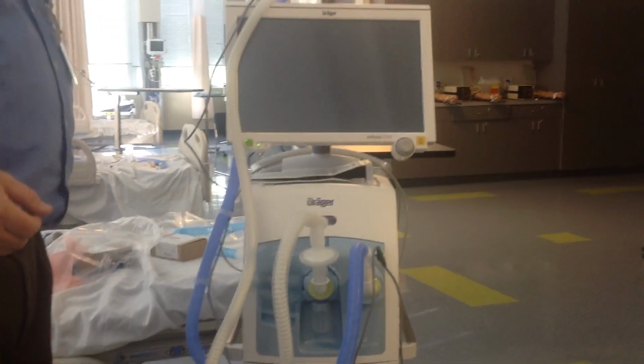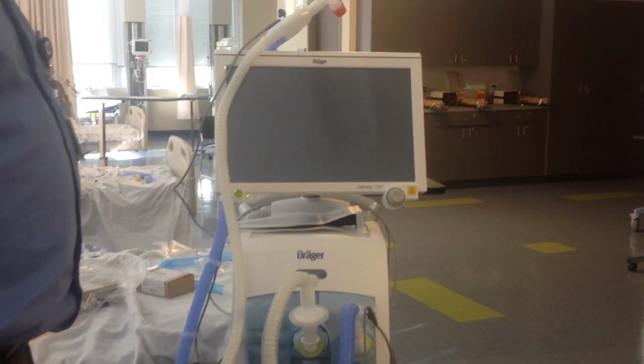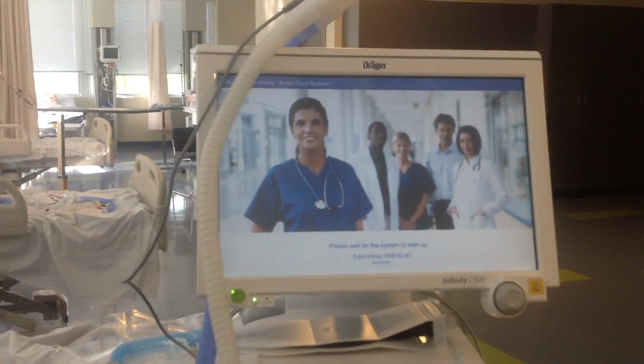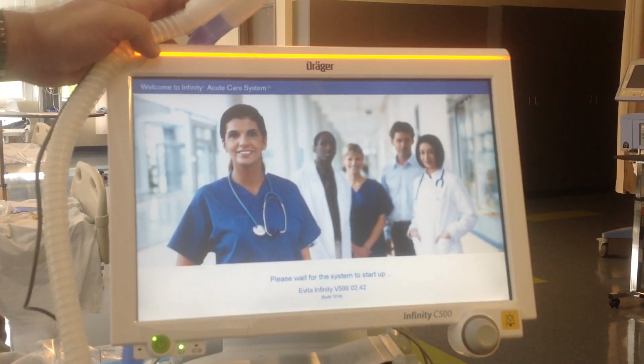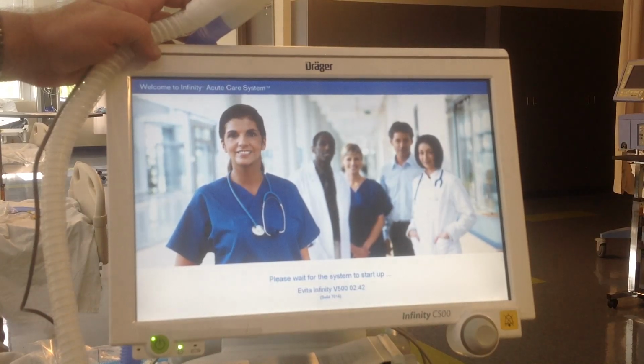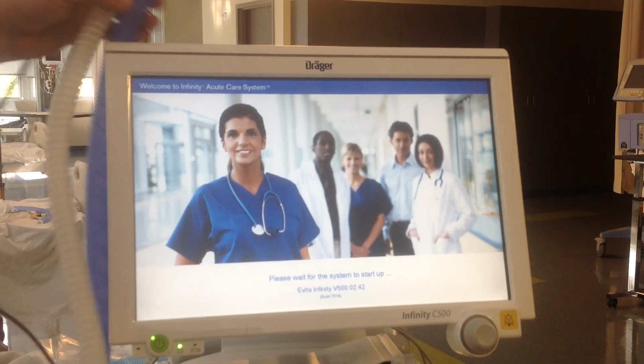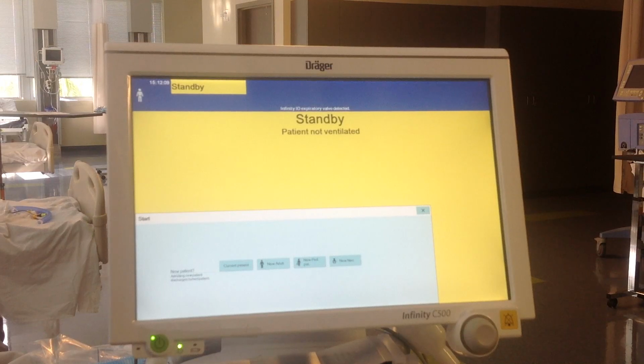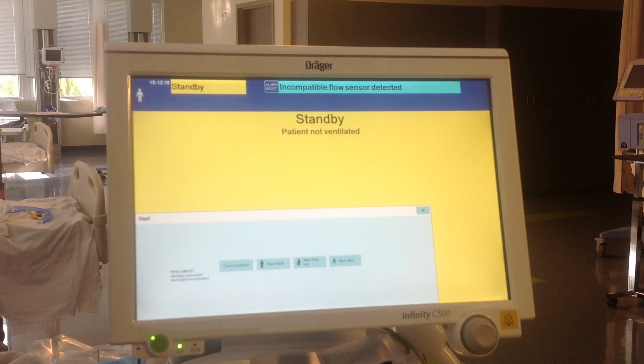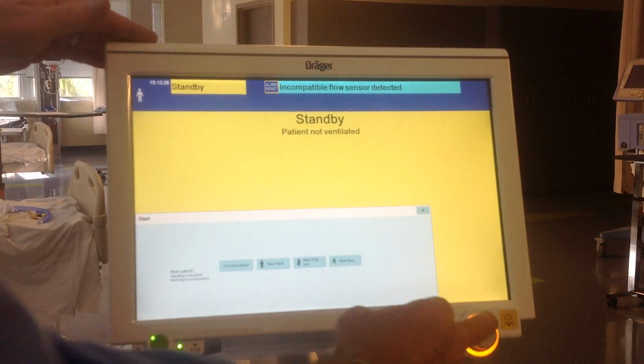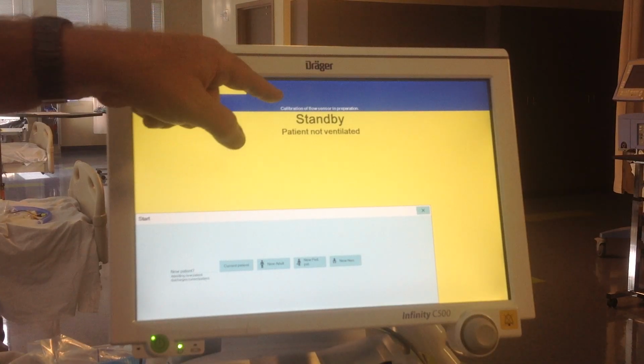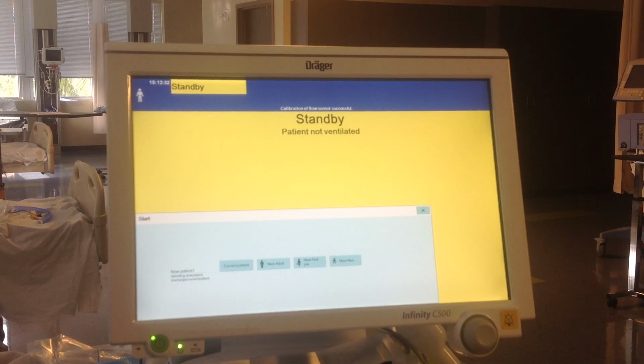Okay, we're going to raise our tripod and zoom in on the screen so you can see the screen better. Okay, patient not ventilated. What this is saying is that the incompatible flow sensor detected. All that is saying is basically our flow sensor is old and should not be used. I'm going to acknowledge it. Calibration of flow sensor in progress. Calibration of flow sensor successful.